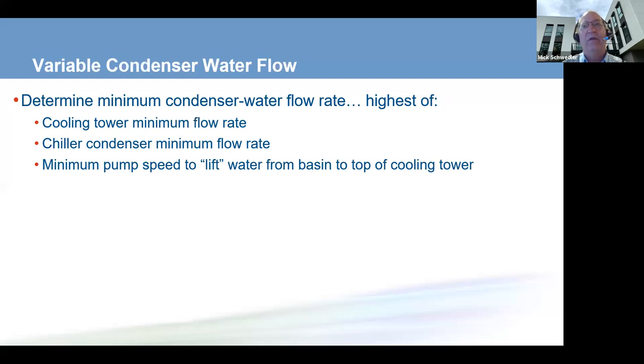The next one is stay above the chiller's minimum condenser water flow rate. We talked about that earlier. If you go below the minimum flow rate, heat transfer gets poor, the efficiency gets worse, the refrigerant temperature and pressure in the condenser go up because the approach temperature goes up, and you end up having unstable chiller control.